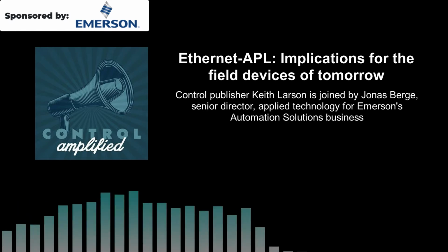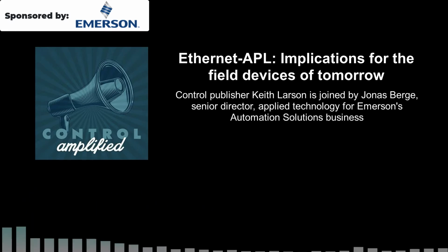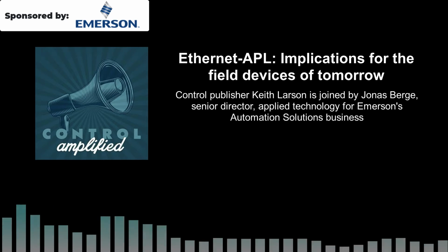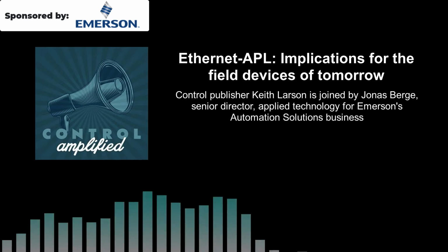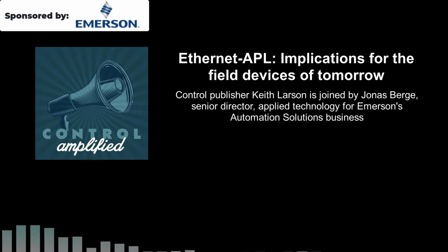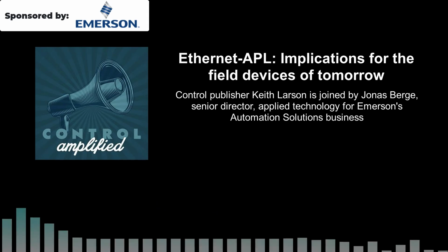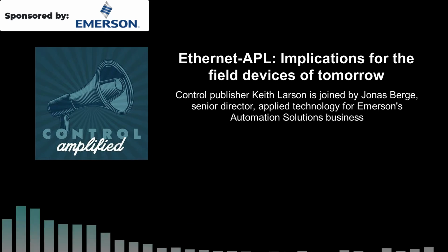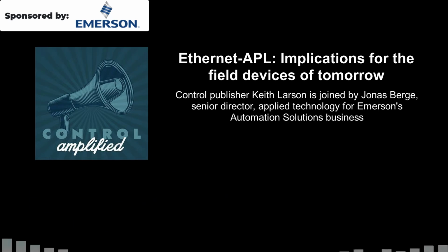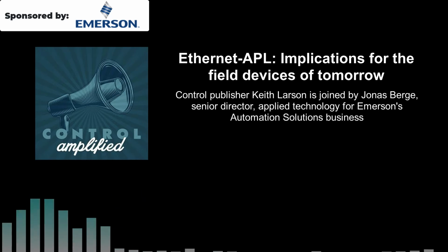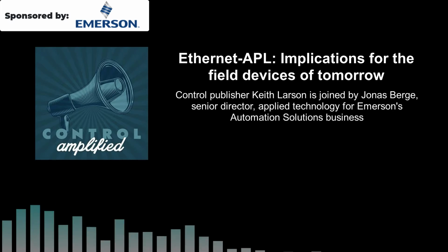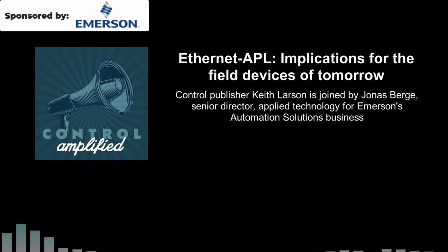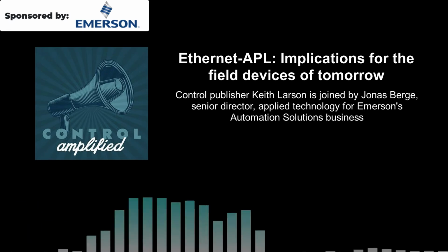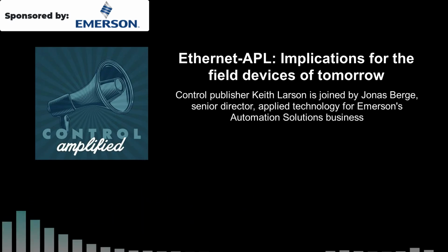For the power supply, I'm glad you brought this up because it's important, but often forgotten as we get all excited about bandwidth. Ethernet-APL provides not only communication, but also power over the same two wires, just like 4 to 20 milliamp HART loop-powered and fieldbus bus power. For two-wire loop-powered HART devices, their power is limited by the 4 to 20 milliamp signal. They must be able to operate on less than 4 milliamps, which is not much, and it limits what type of devices can be two-wire loop-powered. Now, depending on the application, APL provides more than half a watt or more than 1 watt of power to a device, which is almost like 10 to 20 times that of 4 to 20 milliamp devices.